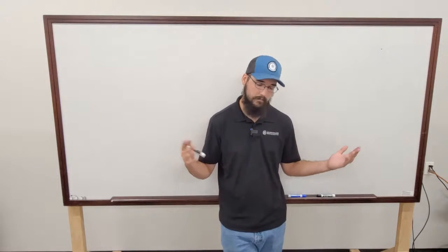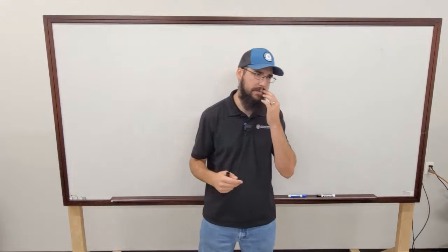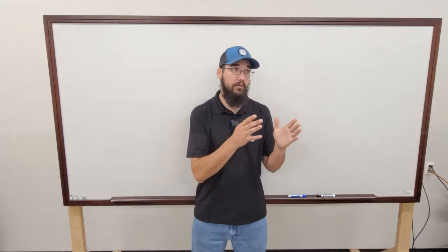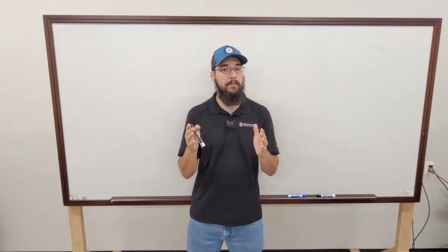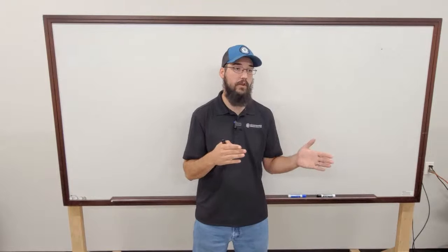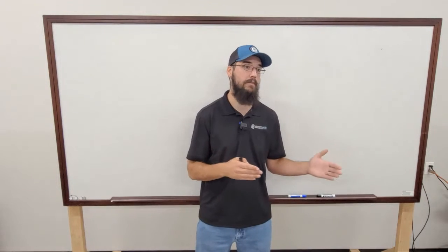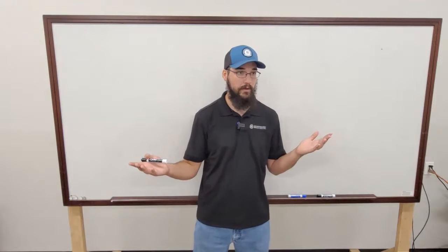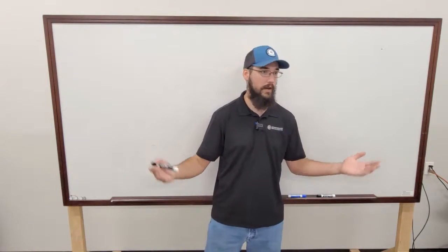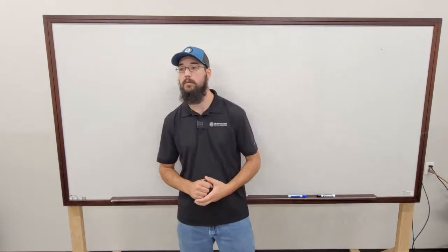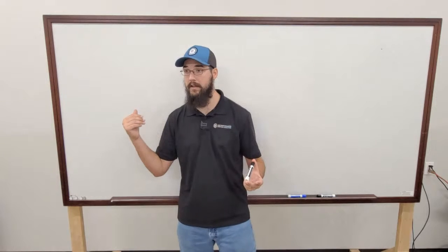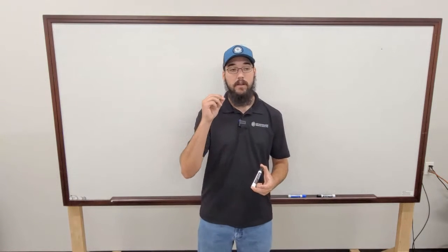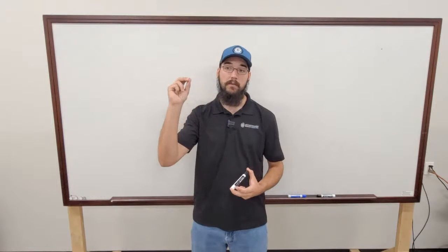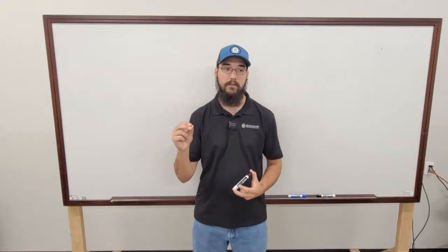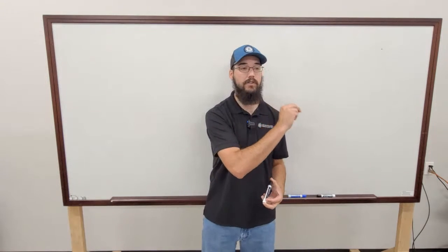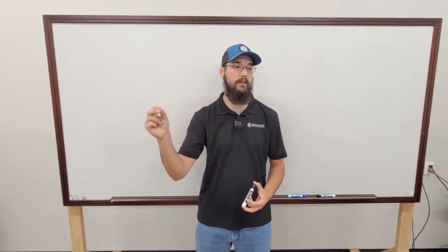Mine is starts. And some of them don't even give you the option to base it. You either do a dedicated lead lag where one circuit is your dedicated lead circuit. So that is one option. Or you do a balanced load where it cycles between the two based off of starts or hours or whatever it is. You could also have a system where, if it's tied into BACnet or Modbus or the communication system, that could be coming from the automation. And they can write to a point in the chiller where the automation decides who gets to cycle as our lead.